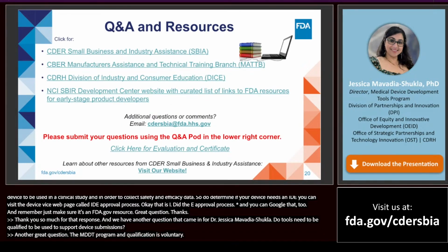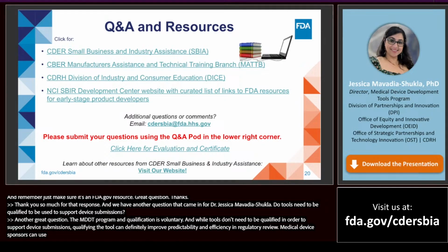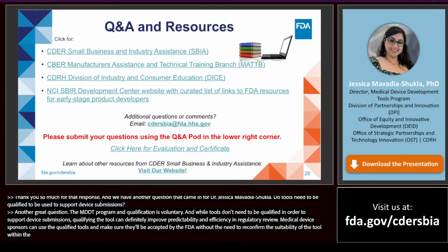And while tools don't need to be qualified in order to support device submissions, qualifying the tool can definitely improve predictability and efficiency in device development and regulatory review. Medical device sponsors can use the qualified tools and be sure that they'll be accepted by the FDA without the need to reconfirm the suitability and utility of the tool within the same context of use. So it certainly is helpful, but they do not need to be qualified to be used to support a device submission.